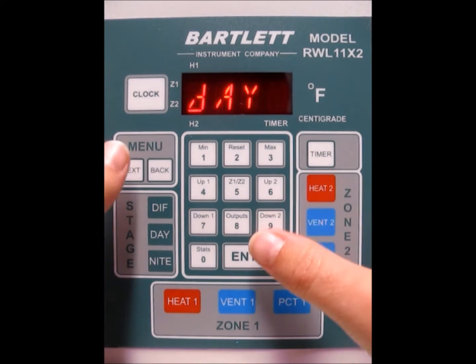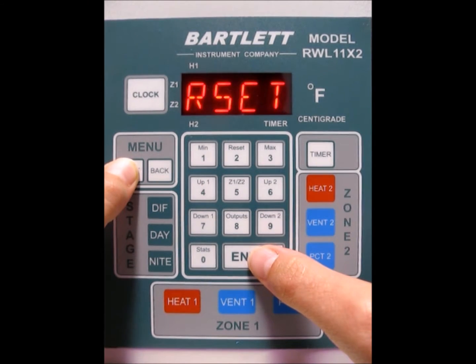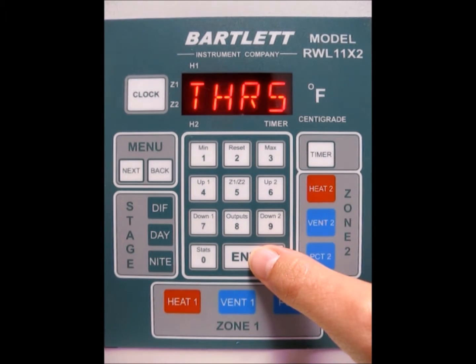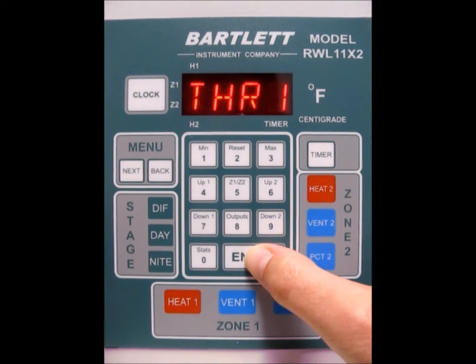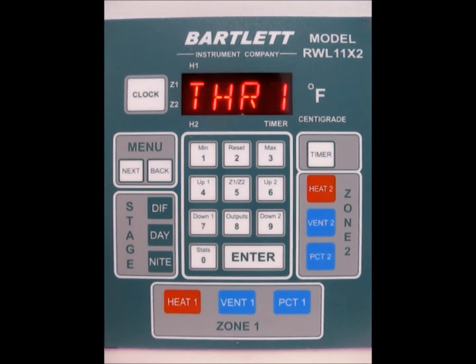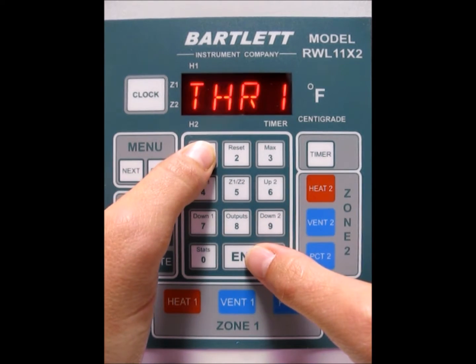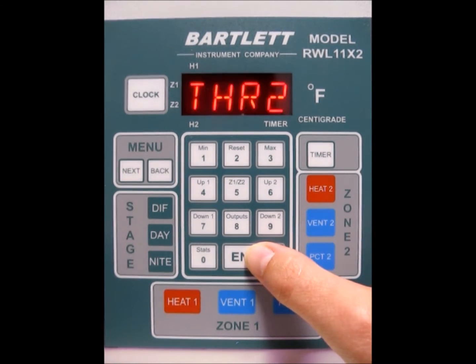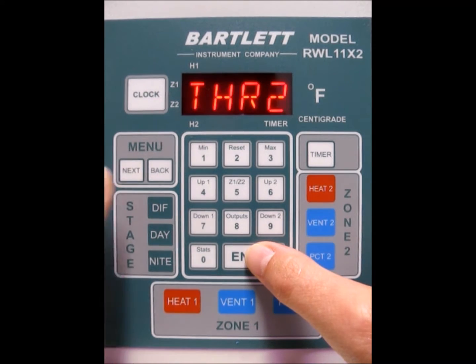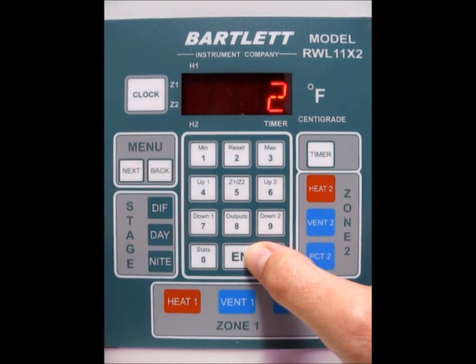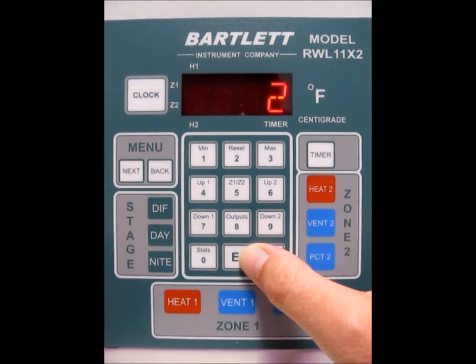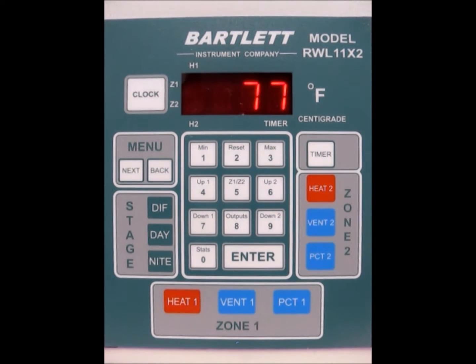The next thing we need to do is check our threshold time. Press the next button until THRS, standing for threshold, appears, then press the enter button. This is the amount of time before it will move on to the next percentage — we'll program 5 percentages for each proportional output. I want a minute between each one, so push 1. For proportional output number 2's threshold time, we'll do 2 minutes. Press enter and we're back at the idle screen.